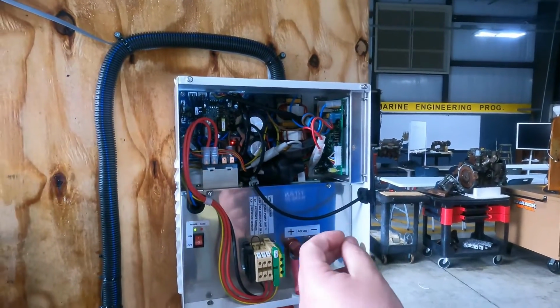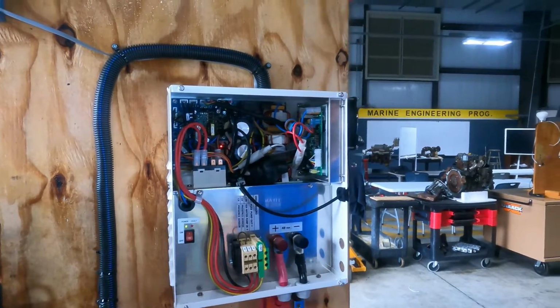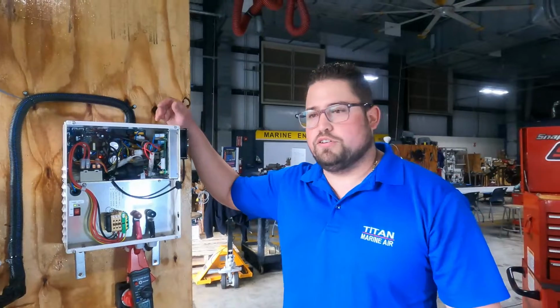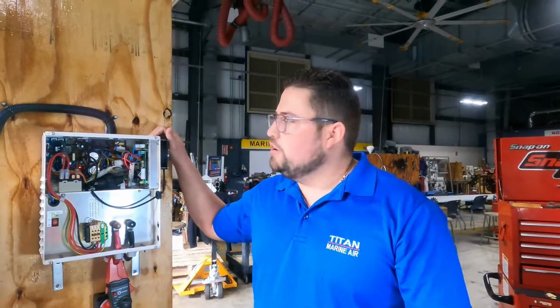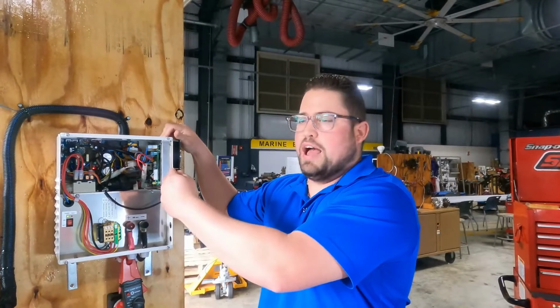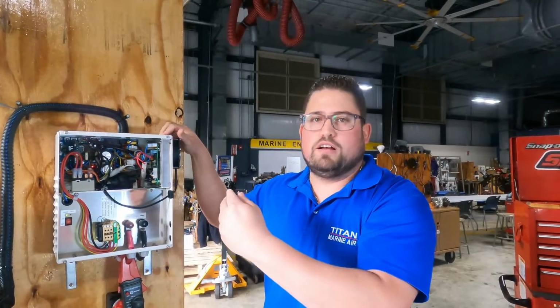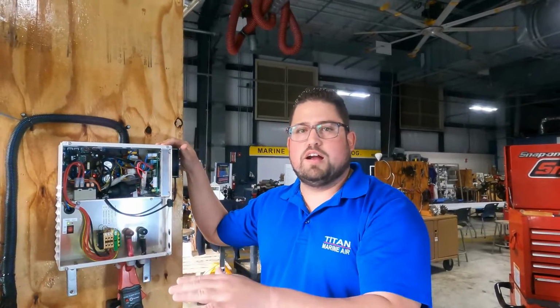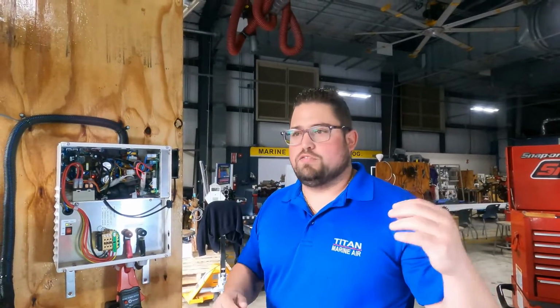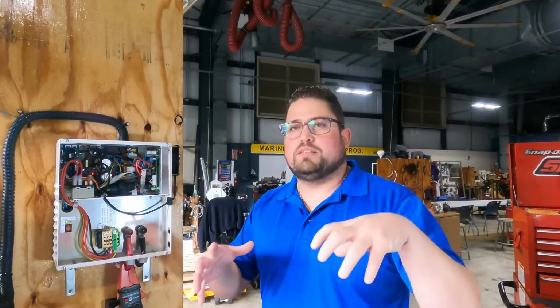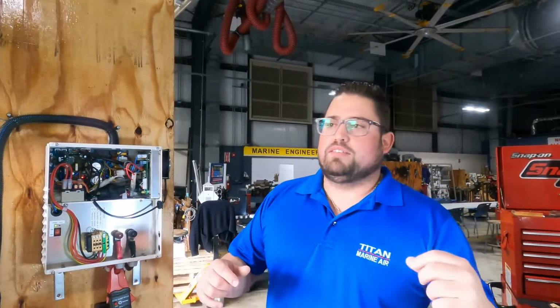So the brains of the unit will command our frequency drive to give a specific speed to the compressor depending on the ambient temperature and the set point. So depending on which set point you have on your unit and the related ambient temperature, the brains will decide, okay, we have to work full load, and as we get closer to a set point, we're going to start decreasing the RPM, creating a more linear consumption line. And this would also keep the ambient temperature steady, versus having the temperature inside your cabin go down and then having to rise up 2 degrees for the compressor to start.